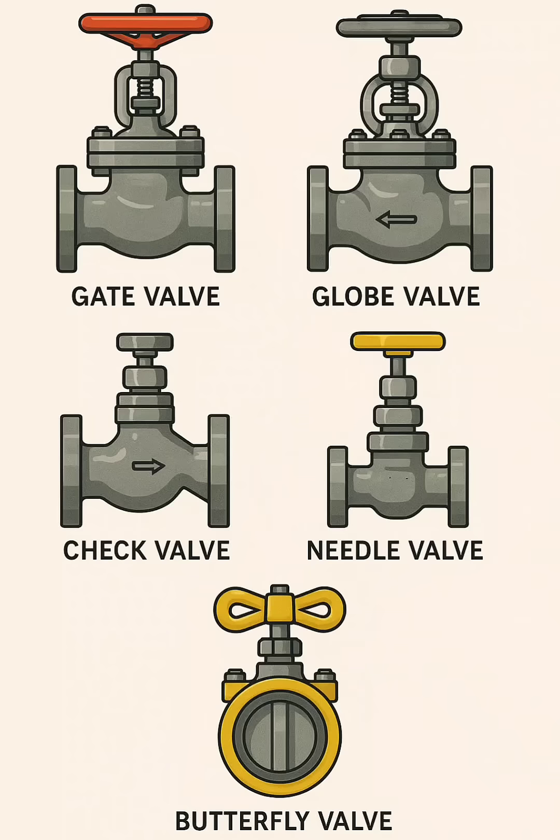Flow: More pressure drop compared to gate valve because of the change in flow direction. Use: Good where flow control and frequent operation are needed, e.g. choke lines, cooling systems.